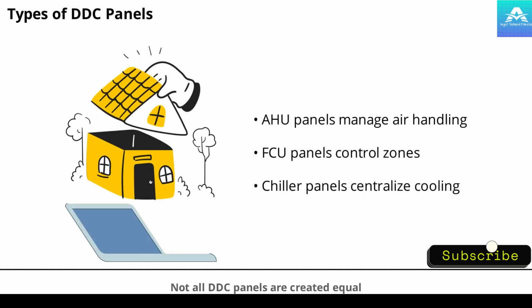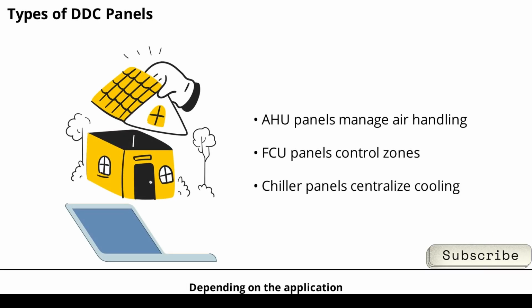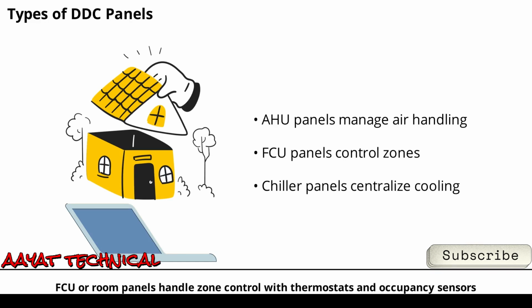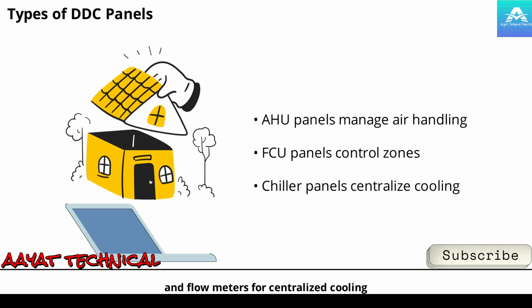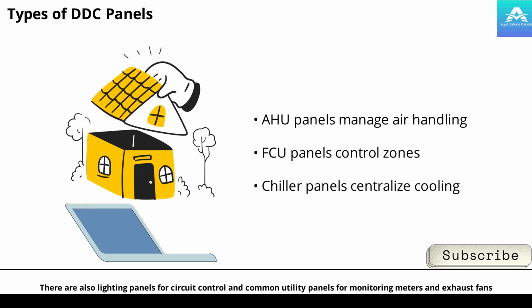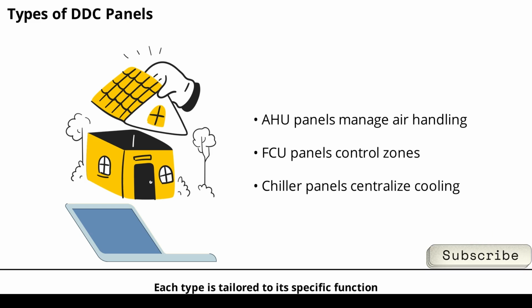Not all DDC panels are created equal. Depending on the application, you'll find different types. AHU DDC panels control air handling units, managing fans, dampers, and temperature sensors. FCU or room panels handle zone control with thermostats and occupancy sensors. Chiller plant panels integrate chillers, pumps, and flow meters for centralized cooling. There are also lighting panels for circuit control and common utility panels for monitoring meters and exhaust fans. Each type is tailored to its specific function, ensuring efficient and targeted control throughout the building.